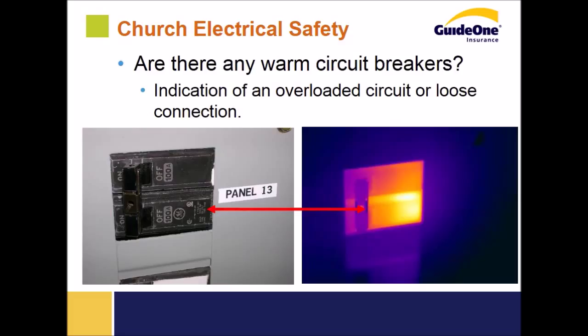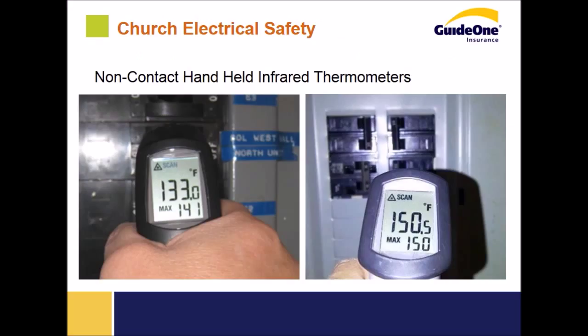Another kind of obvious indication that you've got an electrical problem is the presence of warm circuit breakers. In this case, we've got a hot breaker, and we happen to have a thermal image of it. It's 148 degrees Fahrenheit. This can be caused by a couple of different things. Most commonly, it's an overloaded circuit or a loose connection behind the panel.